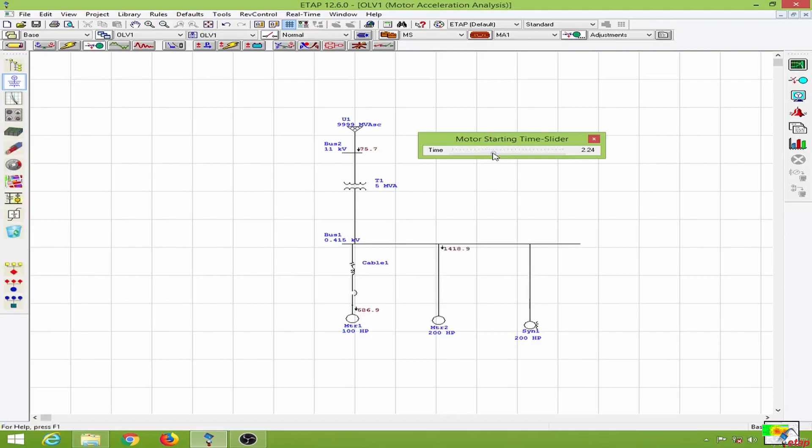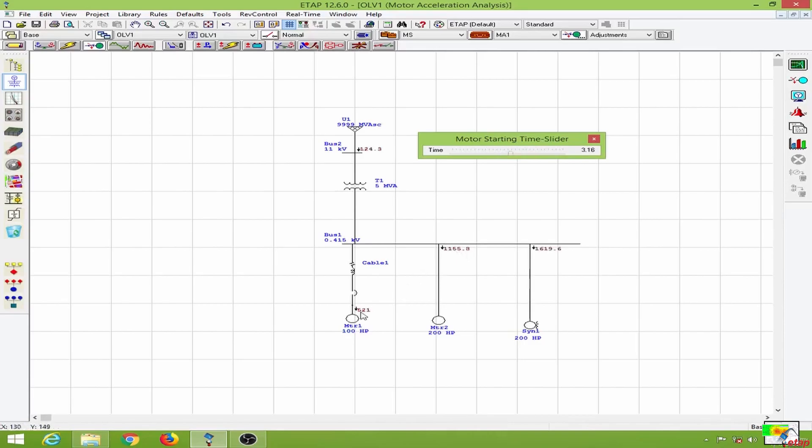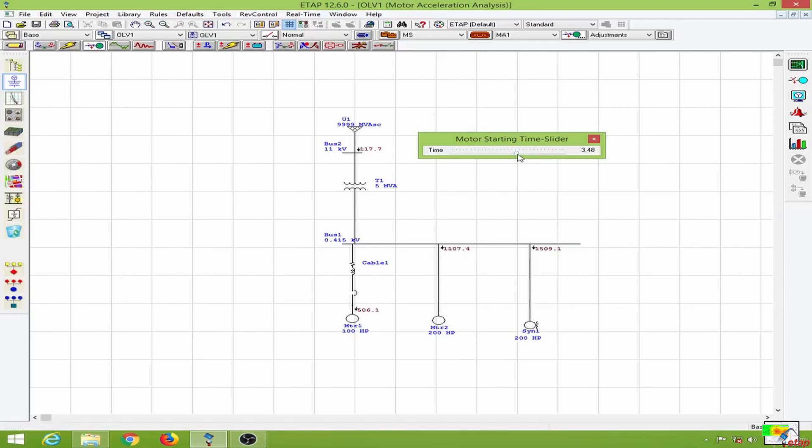Now at 2 seconds we have the inrush current for the motor 2. Going back to 3 seconds you can see this has reduced, and the inrush current for motor 1 and motor 2 have been reduced. Then you can see the inrush current for the synchronous motor as well, and this also gets reduced with time.